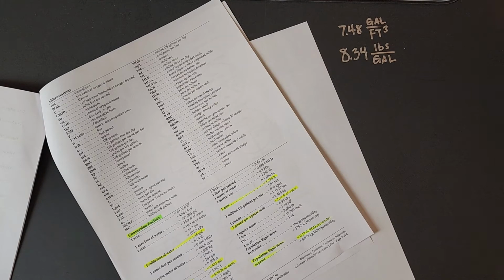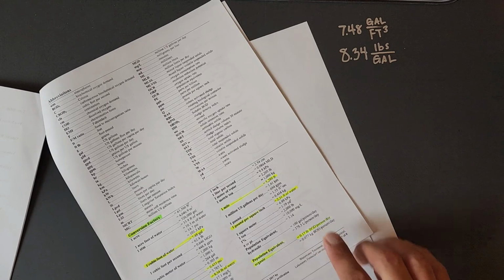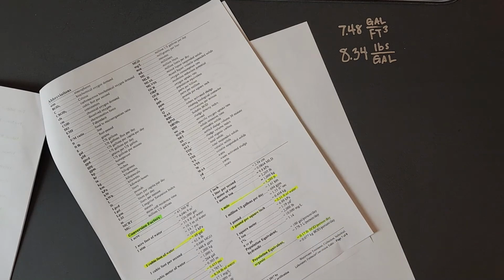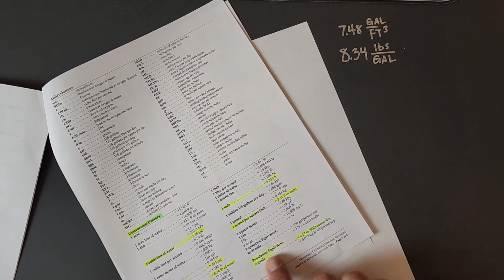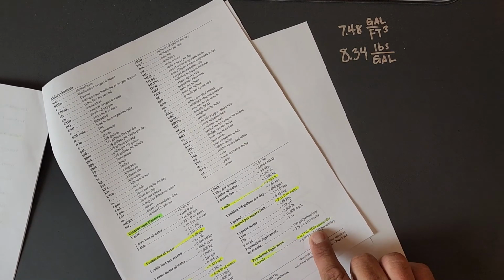And our conversion factor is 0.17 pounds BOD per person per day. What does that mean? Well, that very simply means, on average, each and every one of us will flush 0.17 pounds per day of solids. We poop, and on average it's 0.17 pounds worth of poop. So everything I ate yesterday, everything I consumed has been digested, and this morning I pooped it, flushed the toilet, let it go into the collection system, job security. So this is an important conversion factor to understand in the wastewater treatment process, especially as a wastewater treatment plant operator.